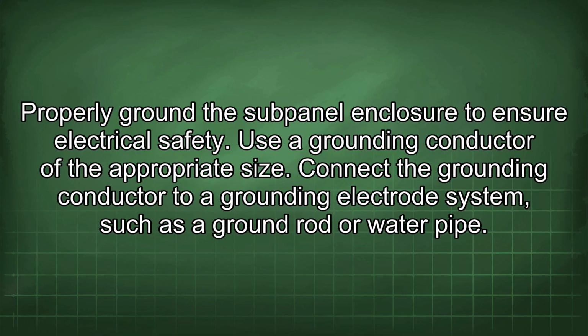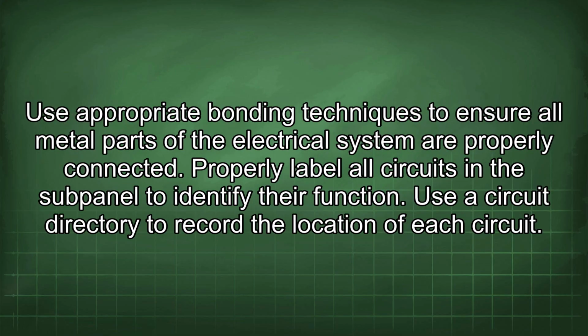Properly ground the subpanel enclosure to ensure electrical safety. Use a grounding conductor of the appropriate size. Connect the grounding conductor to a grounding electrode system, such as a ground rod or water pipe. Use appropriate bonding techniques to ensure all metal parts of the electrical system are properly connected.